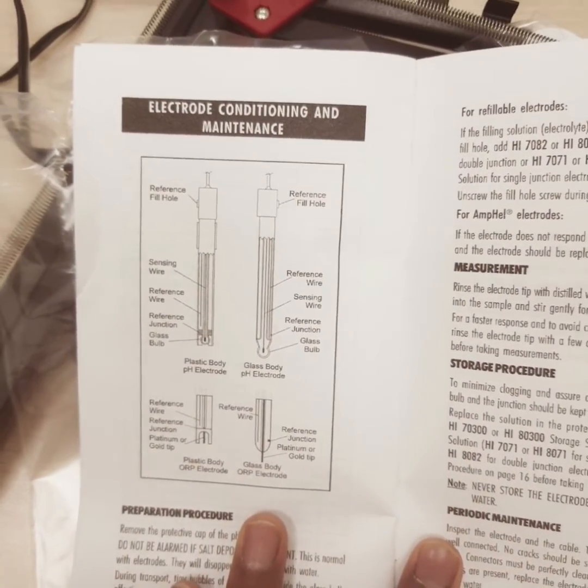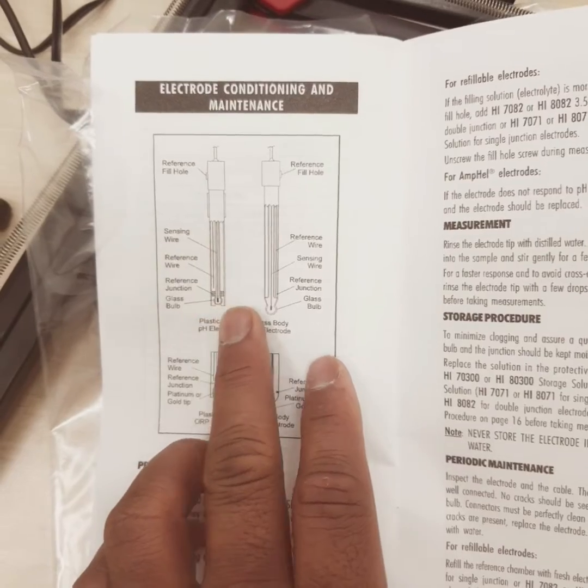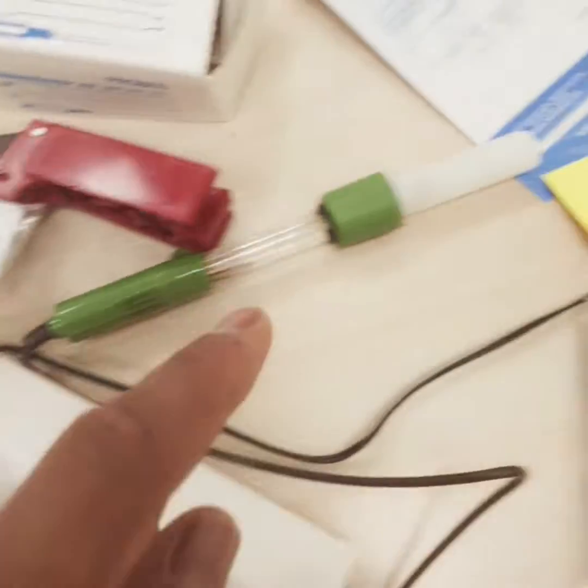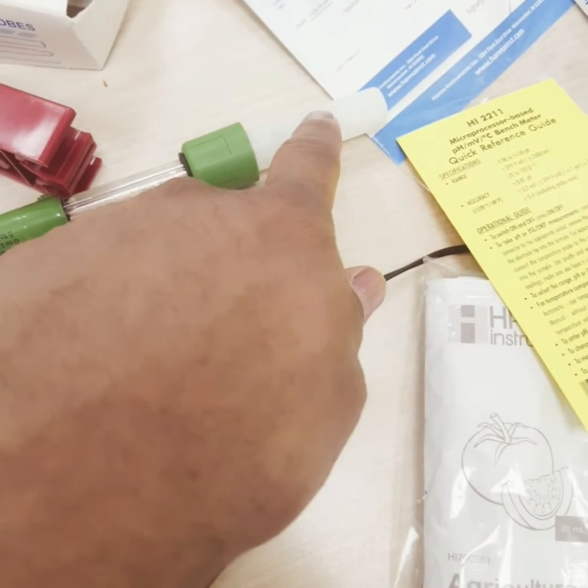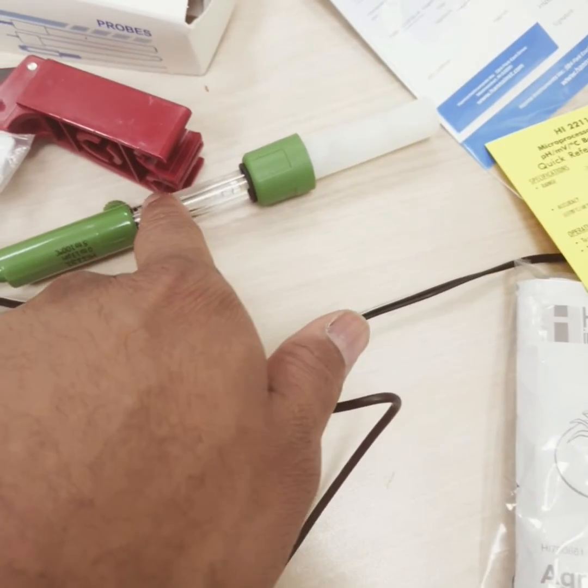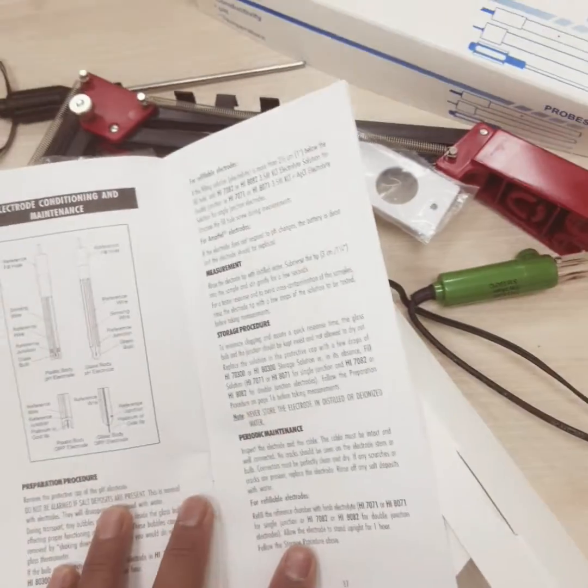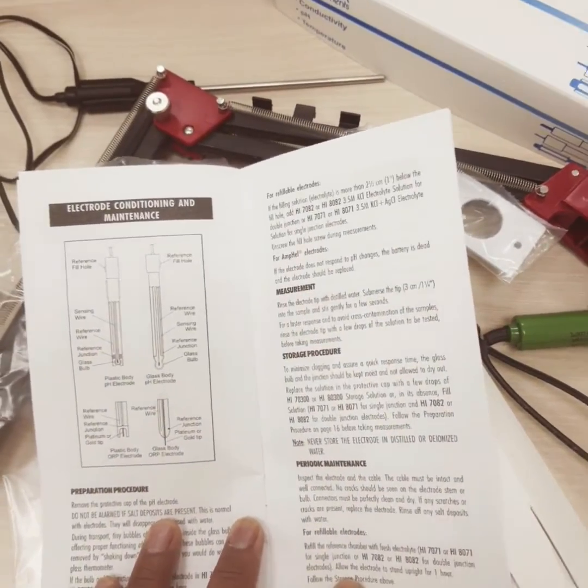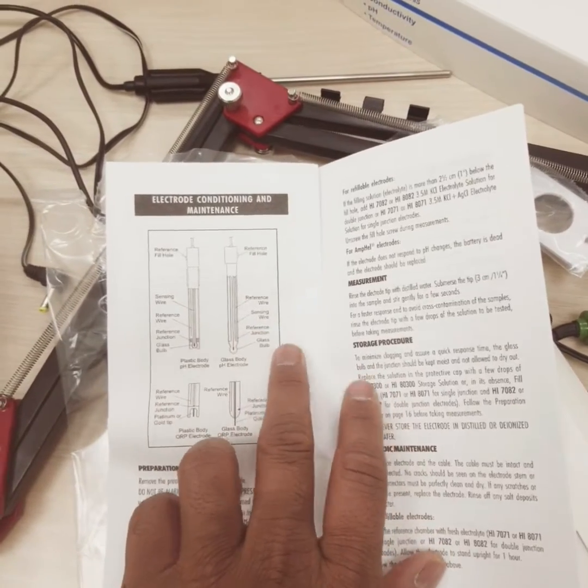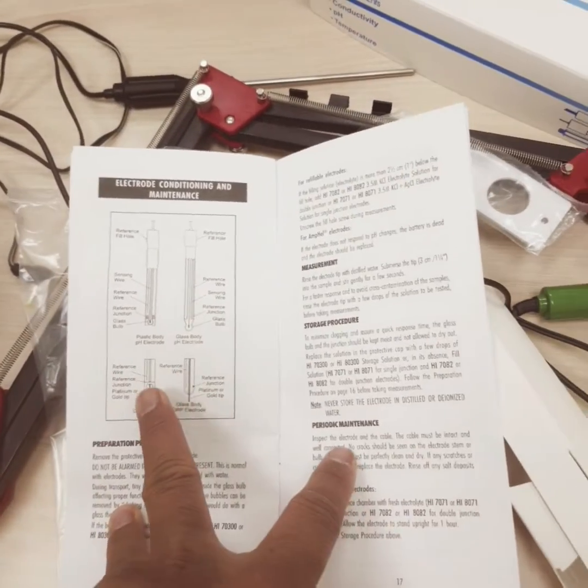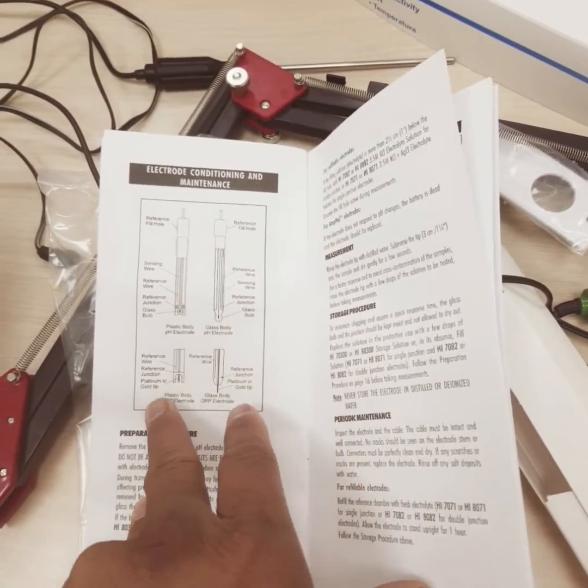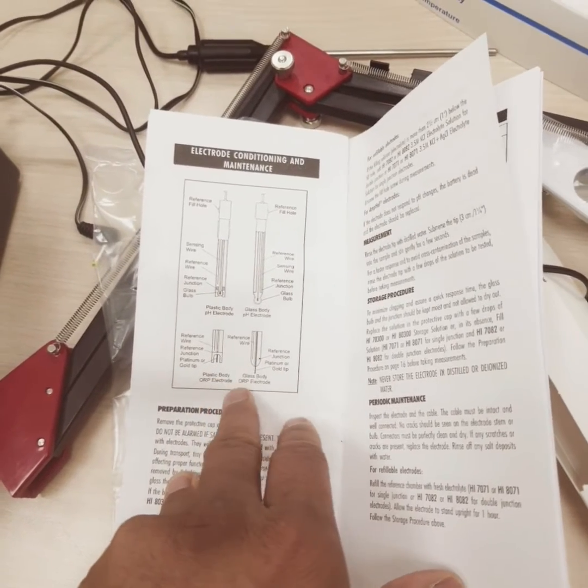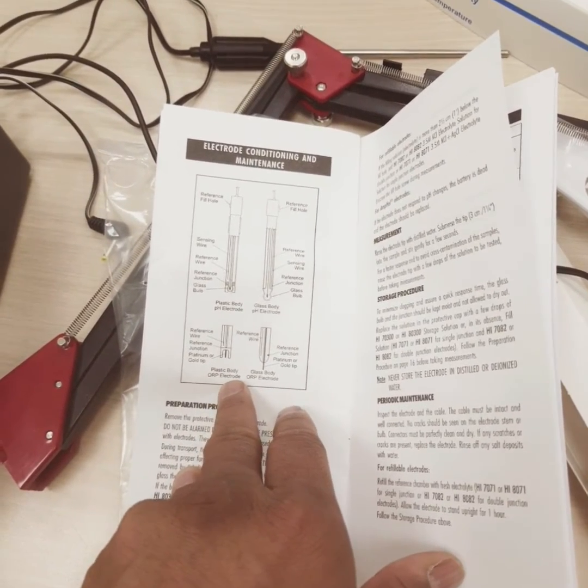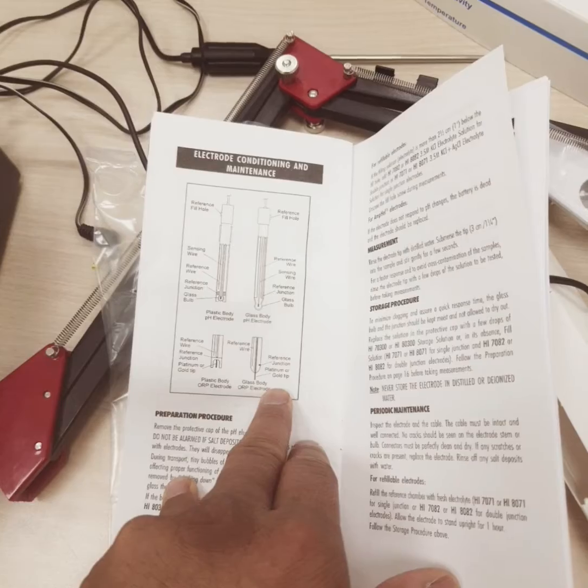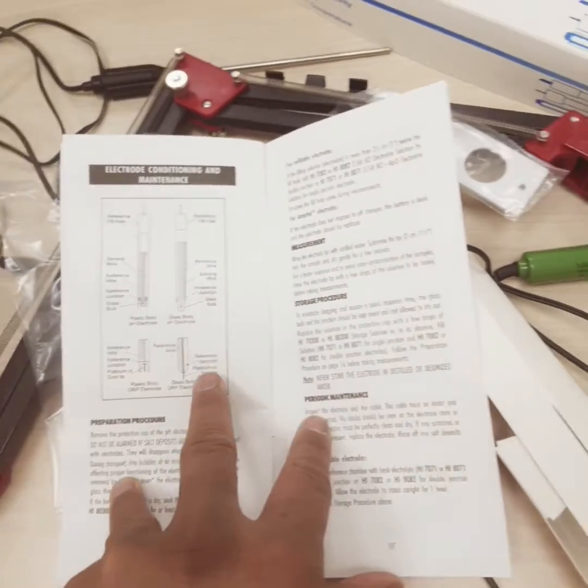And here you can see this is my reference, and then sensing wire, then we have junction, then we have glass bulb. So inside you can see this here, this is a glass bulb, and this is my reference wire, and you can see the reference junction also, the glass bulb, and then reference wire. And this tip basically is of platinum or gold, and this plastic body, or we can say ORP electrode, glass body or ORP electrode.